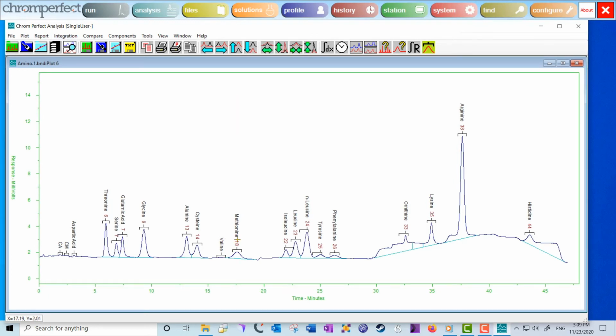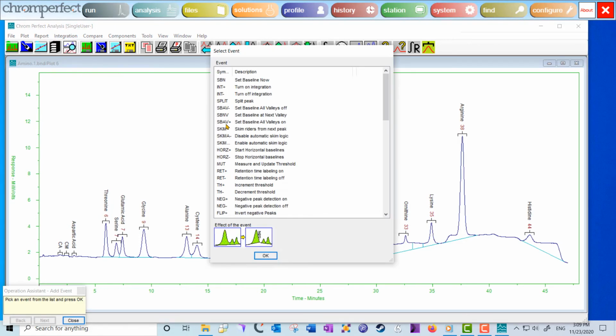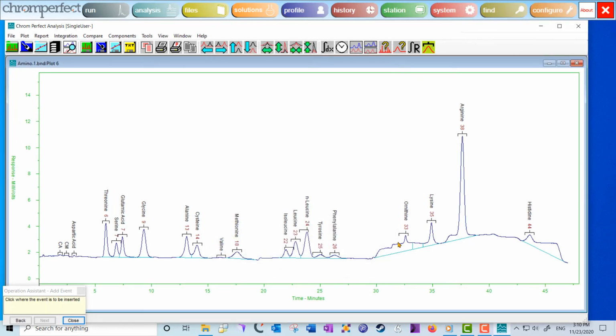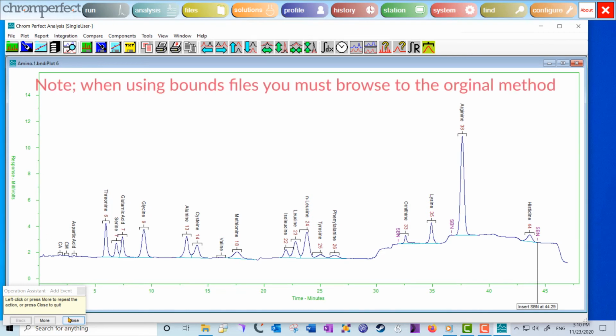Pull down the integration menu and choose Insert Event. Select a suitable event to accomplish the desired effect and insert it at the appropriate time on the chromatogram. On the Select Event form, there is a thumbnail at the bottom that shows the effect of the event. You can place the event with the left mouse button and then confirm the operation with the right mouse button. There is also an operation assistant which explains the process. When you have added all the necessary events, then save your method file as described above.